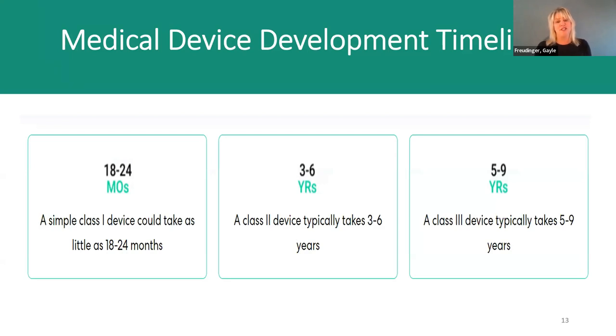We often get the question, how long does it take to develop a medical device? We get that question quite a bit. And medical device timelines really vary by the type of device, how many resources you have in-house, how many experts are developing the device, the regulatory process, available funding, and other factors. Here are the medical device development timelines for class one, class two, and class three devices. And you can see here, a class one device can take maybe 2 years or less to develop, 18 to 24 months, where a class two device can take 3 to 6 years to develop, possibly longer, depending on your resources, et cetera. And then a class three device typically takes 5 to 9 years to develop because it's got a high risk. A lot of extra testing is going to need to be done.